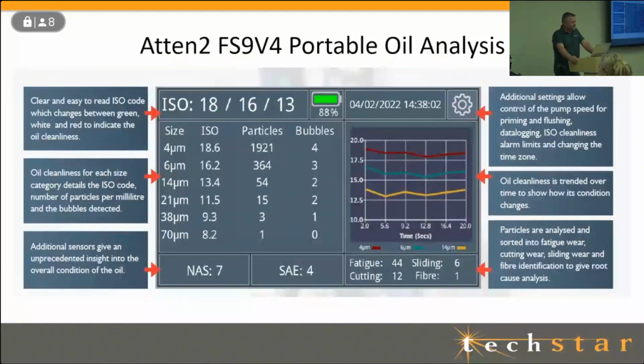If you look over to the right-hand side, we'll start in the middle of the screen. You can let this system continuously run so that you're constantly trending these samples. The device takes a sample about every 2 minutes. So every 2 minutes, this trend screen will update. And if you look just below the trend screen, you'll see the particles and the wear particles and what they were broken down into. There are 4 categories there. If it's more of a fatigue, say a rolling element bearing that's failing on you and releasing more of those fatigue type particles in the fluid, you'd see that quickly, which looks like kind of what we're seeing here.